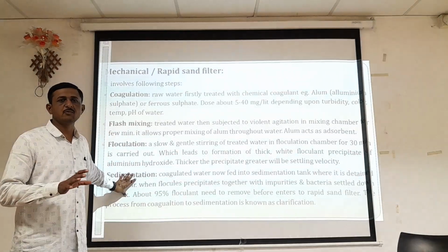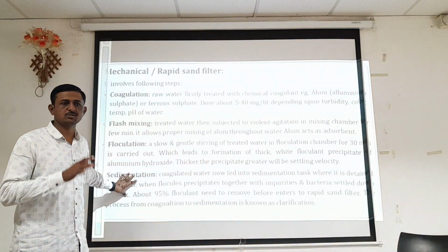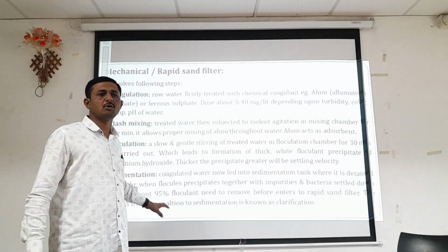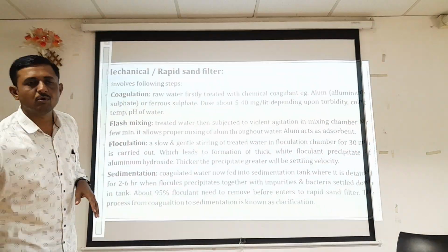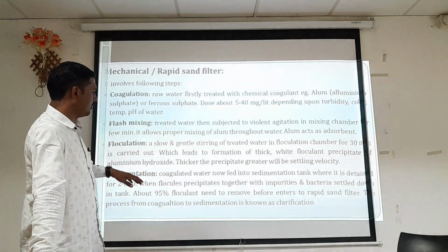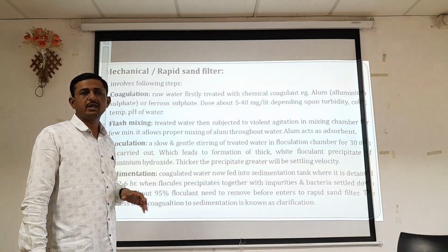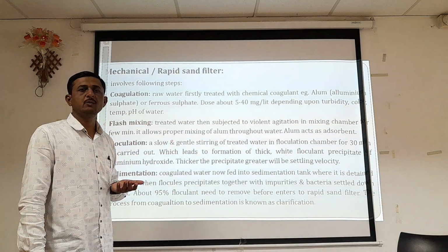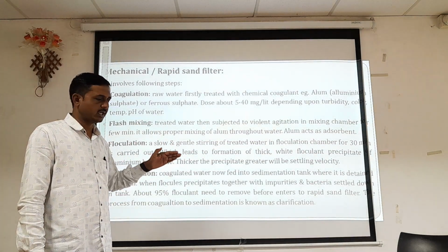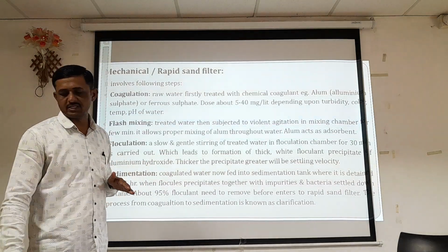the water remains for at least 2 to 6 hours, so that the flocs which are formed in the water settle down at the bottom, and about 95% of the different impurities, in the form of suspended particles or bacteria, are expected to settle down at the bottom of that sedimentation tank.